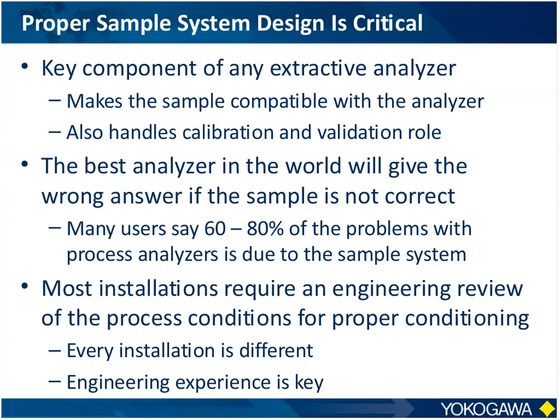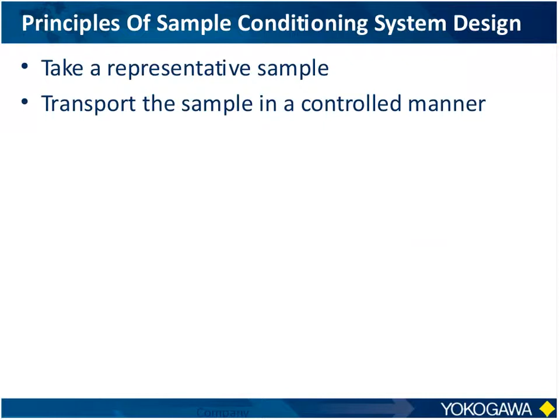So one of the things I want to do is just talk a little bit about sample systems, some of the things involved. Again, we want to make sure we take a sample out of the process. Usually it's a pipe or a conduit or a duct or something where I'm taking a sample out. I'm transporting it from the pipe to the shelter where the analyzer is installed. So I need to do that in a controlled manner. Again, I need to condition the sample: temperature, pressure, flow, filtration, whatever's needed.